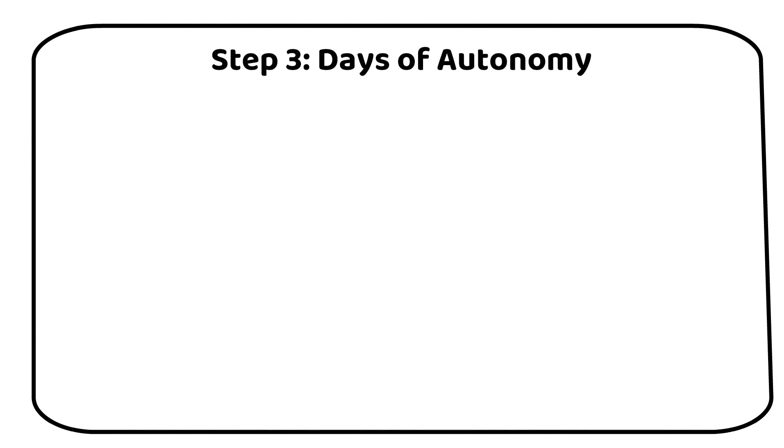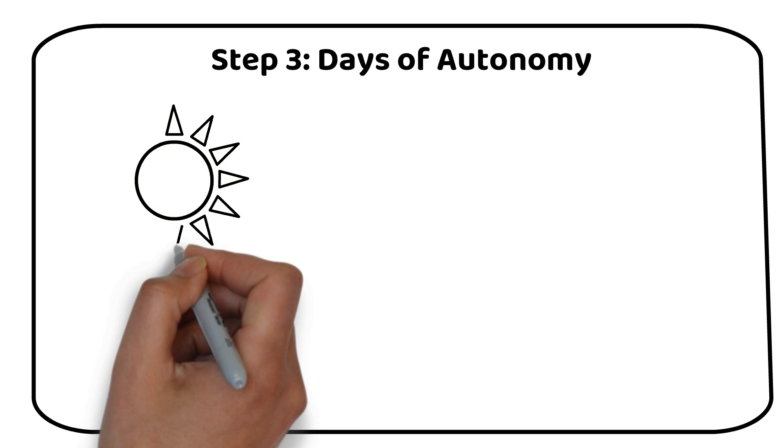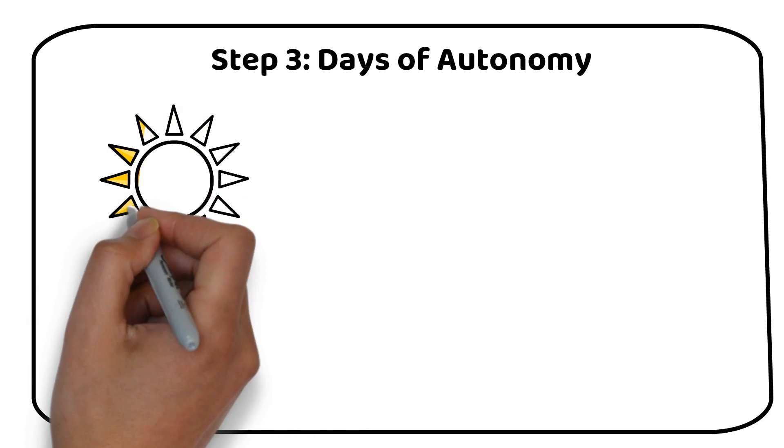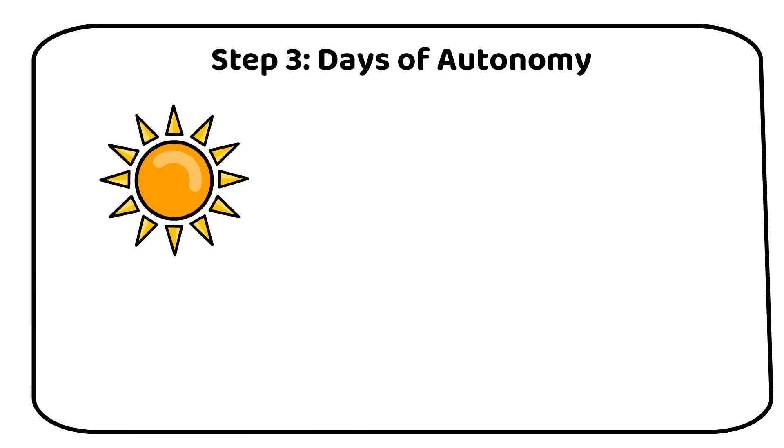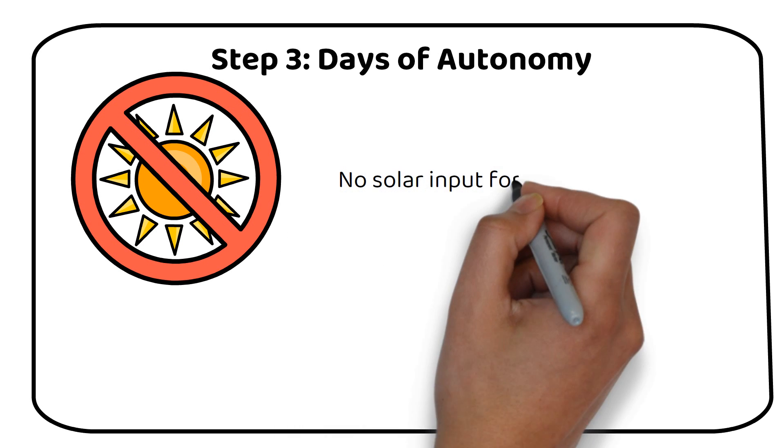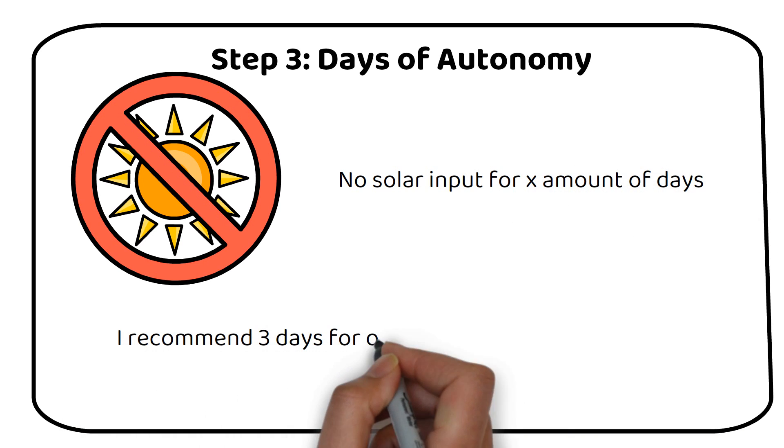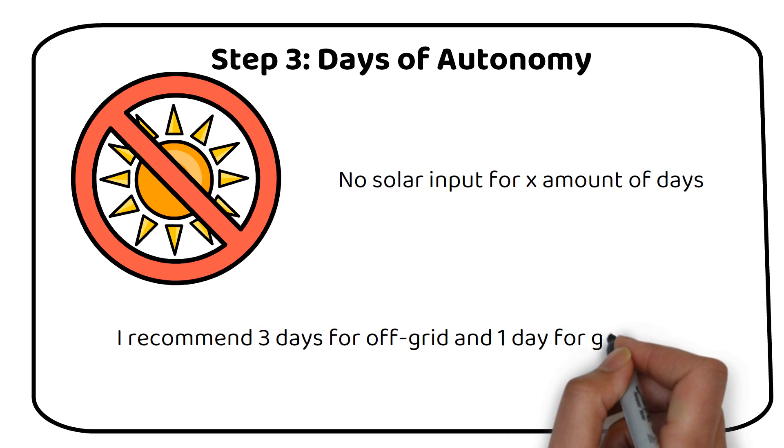Step 3. Days of autonomy. This step involves deciding how many days you want your system to run solely on battery power, assuming no solar input. This is known as days of autonomy. I recommend planning for 3 days to ensure a reliable power supply, even during consecutive days without sunlight. This duration is a balanced choice for most setups. However, if you're connected to the grid, one day of autonomy might be sufficient.